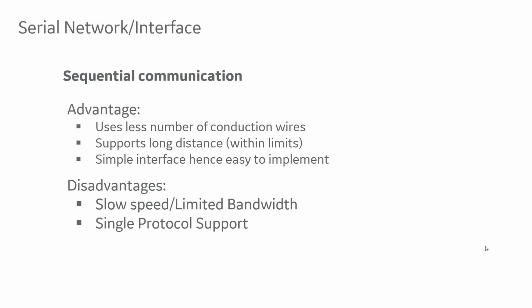Advantages of serial networks when they came out: a limited number of connections—for example, RS-485 would have a send and receive pair, and RS-232 has about 4 or 5 wires, so not a lot of connections. They can go long distances, within limits, and they have simple interfaces that are easy to implement. For instance, when you go in front of a relay to download settings, you connect through RS-232 directly to your computer, or via USB—it's a very simple interface that's physically available to you.